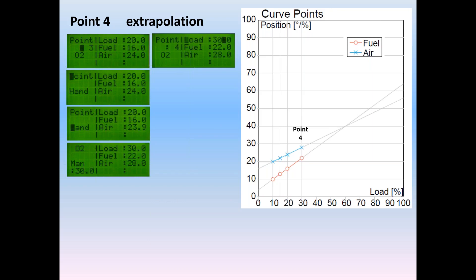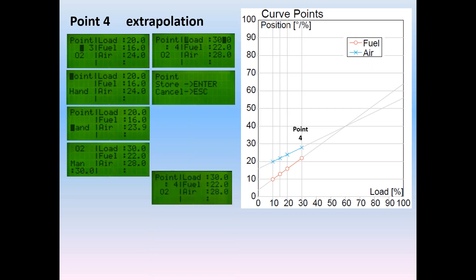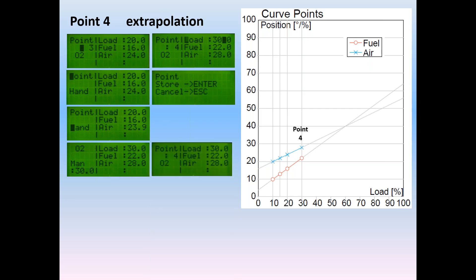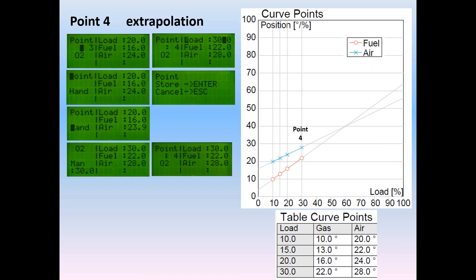Point number four we can do some extrapolation. I want to demonstrate extending an existing curve. Enter the point or on your cursor enters the menu on the point slide it down to the hand option just as we did on point number three. It immediately turns to manual and now you can pick a load number that's higher than anything that you have in the curve and the curve will follow the pre-exit the points previous to it. Take the last two points and extend them and if I went out there to 30, 40, 50 percent you can see in the graph how it just keeps projecting the settings. This is a very convenient way to advance the curves rather than the tedious two degrees on the air, two degrees on the fuel, one degree on the air, three degrees on the fuel, back and forth business. You can simply drive them up in unison at the current rate that they were going based on the previous point. Makes for a very fast curve building. Again you get the point number four. You get your load number set in there. You adjust the fuel and air settings. You escape, hit enter, store the point. Now point number four is in there at 30 percent with the new values and your chart now has four points in it. 10 percent, 15, 20 and 30 percent fire rate.